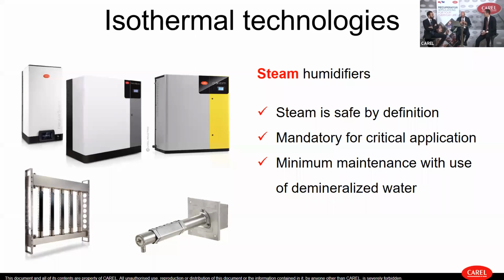Isothermal technology is the most traditional one, because with the isothermal humidifier we introduce steam directly into the supply air, in the airflow. Steam is safe by definition, because steam is aseptic. So steam humidifiers are often mandatory for some critical applications like operating theaters. And they require minimum maintenance if they are used with demineralized water. We have different kinds of steam humidification systems, with heating elements, gas burners, or immersed electrodes. All these technologies can be used in hygienic applications. But steam humidifiers, on the other hand, require by thermodynamics a certain energy consumption.